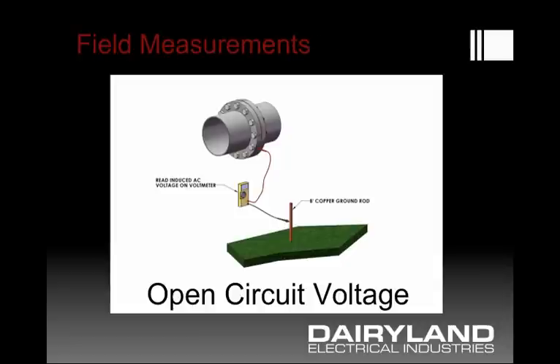A couple of diagrams might help illustrate this. This would represent the open circuit voltage before mitigation that exists between a pipeline and some grounded object — in this case, just a driven ground rod for the purpose of a test. One has to be careful, though: if that ground were not considered to be a very low resistance ground, this may not be the best example. For open circuit voltage, this grounding rod will be perfectly fine, but it may not represent a low resistance ground for bleeding off current.